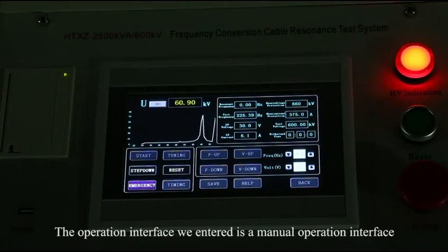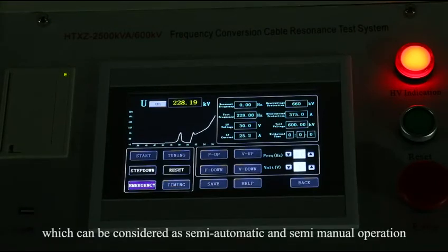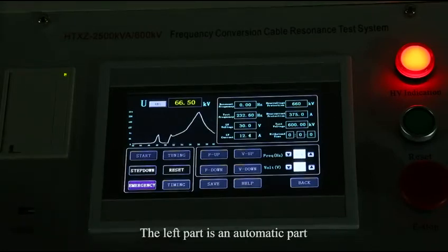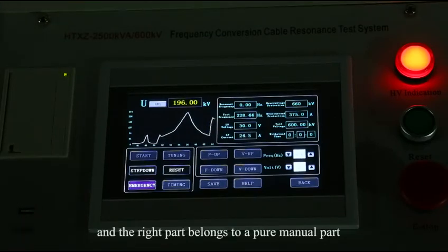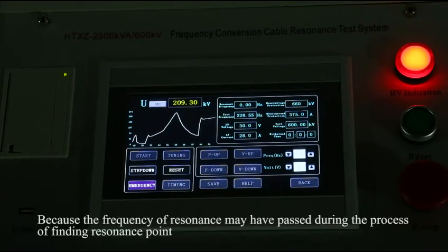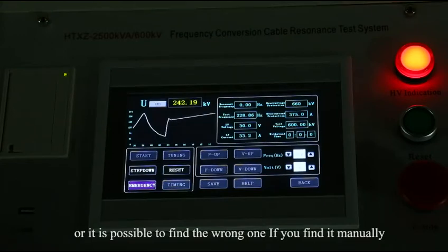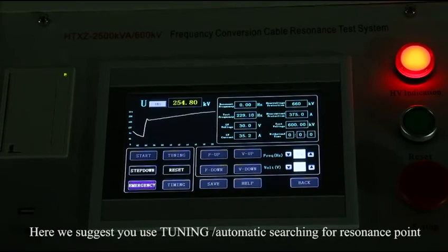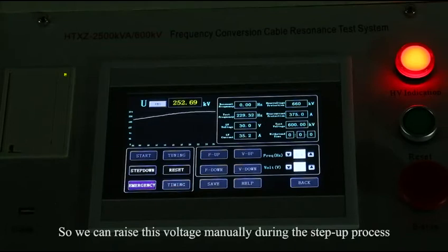The operation interface we entered is a manual operation interface, which can be considered as semi-automatic and semi-manual operation. The left part is an automatic part, and the right part belongs to a pure manual part. Because the frequency of resonance may have passed during the process of finding resonance points, or it is possible to find a wrong one if you find it manually. Here, we suggest you use tuning or automatic searching for resonance points. So, we can raise this voltage manually during the step-up process.